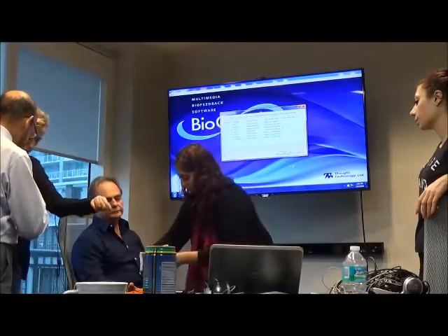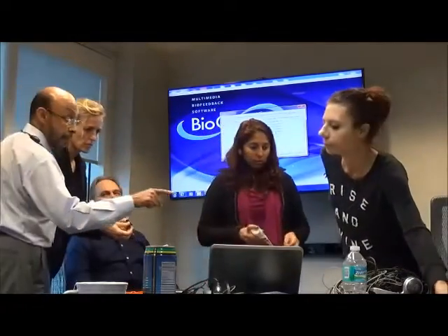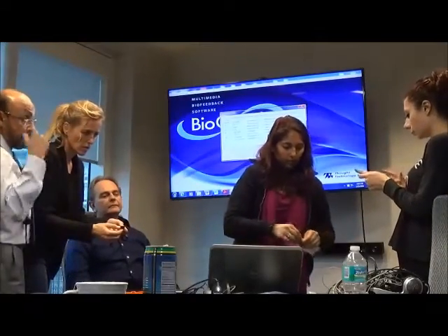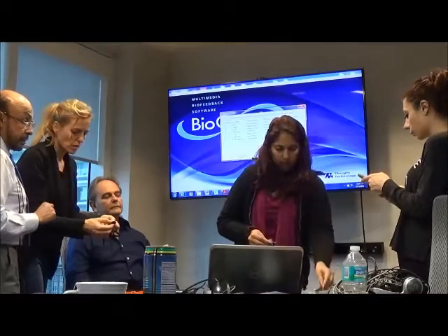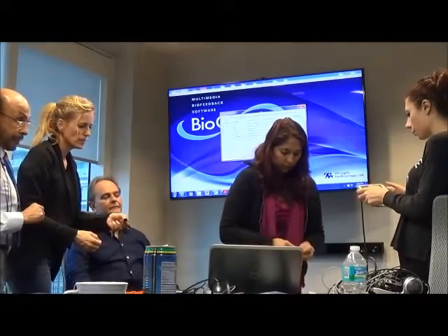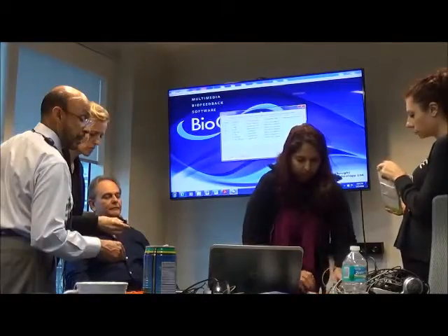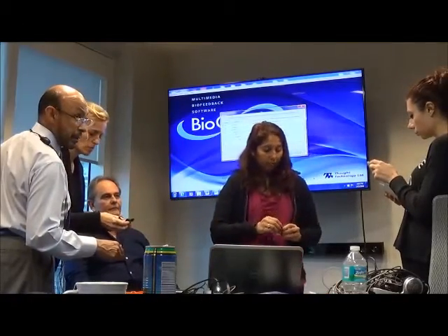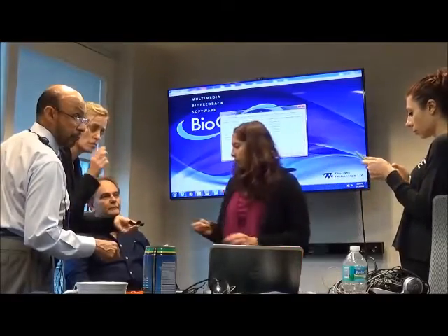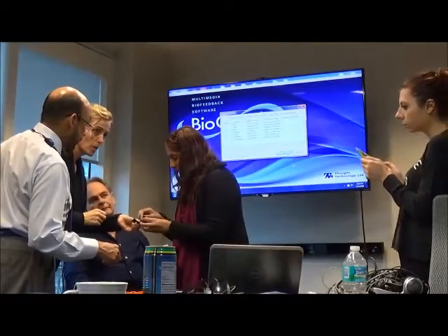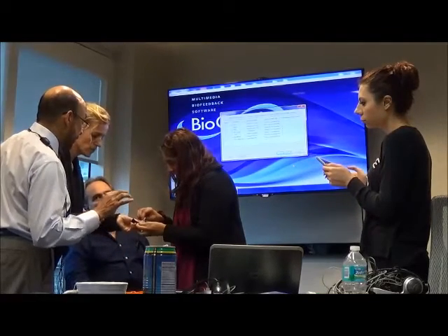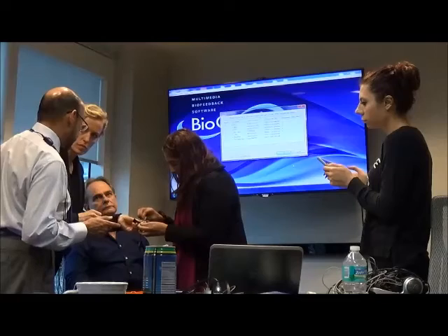You just pass the alcohol pad, you have to clean the residues of the last preparation. And I'm wondering if that was too recent. Well, the discussion about that is just if we're cleaning the sensors with the alcohol pad, it's better to clean it with the one that's not abrasive because the abrasive is going to rub off some of the surface. Because the sensor surface is covered with different things.